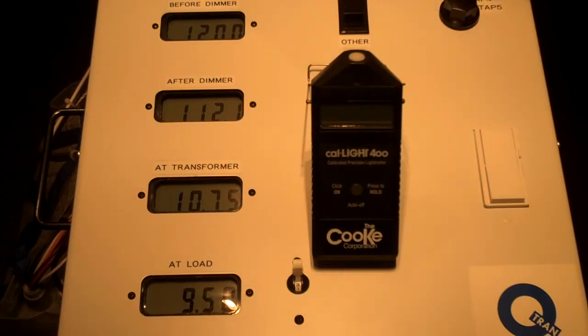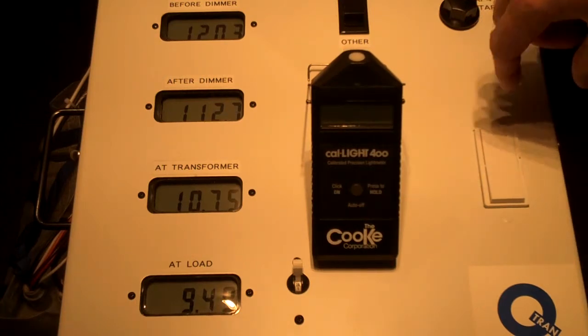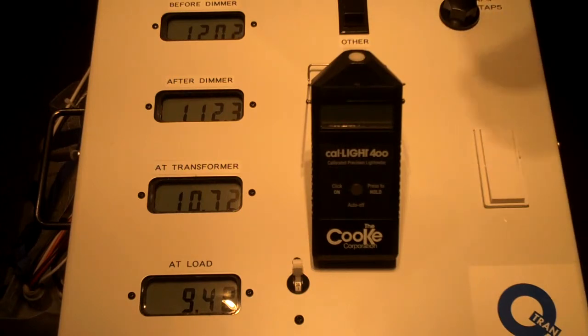So up here you'll see tap 2 through tap 5. Our typical transformer will have 5 output taps. That allows an installing contractor to determine, based on how far away he is and what the load is that he has on that transformer, he can literally pick the tap he needs to deliver the 12 volts, not from the transformer, but at the load itself, because it's really the lamp itself that needs to see 12 volts.